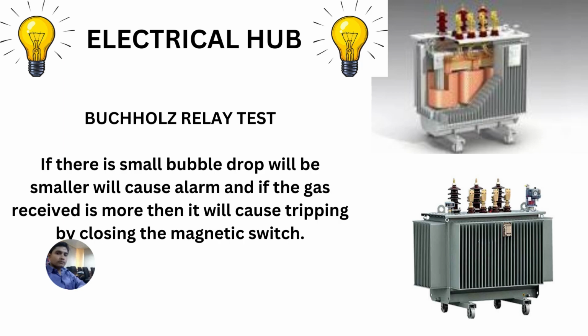Whenever there is a small bubble, it means the fault is smaller, so only a few gases will go and get trapped in the Buchholz relay. So it will cause only an alarm, and if more gas is received, then it will cause tripping. There is a mercury switch which causes the alarm and the tripping. There are also S1 and S2 switches which get closed and provide a signal to the breaker.